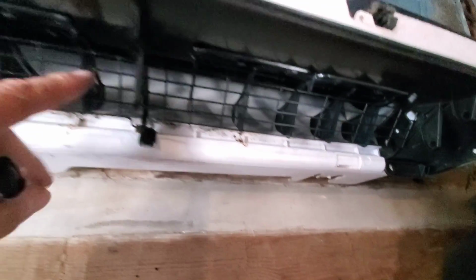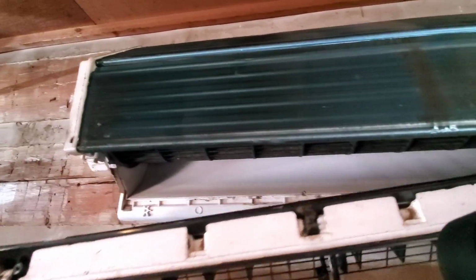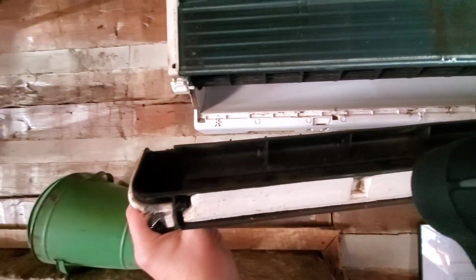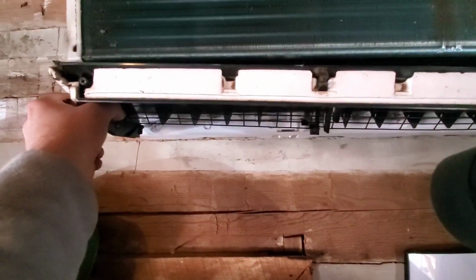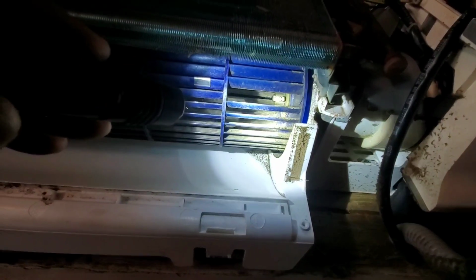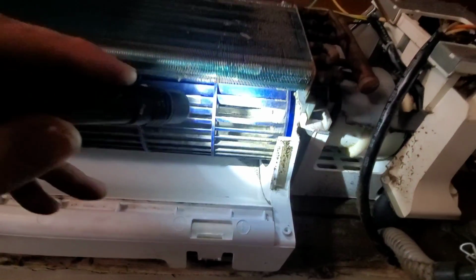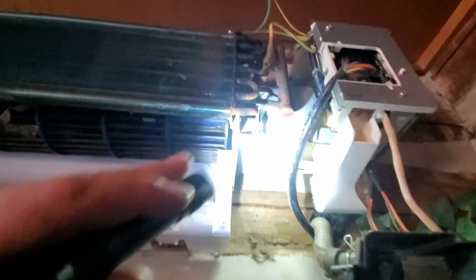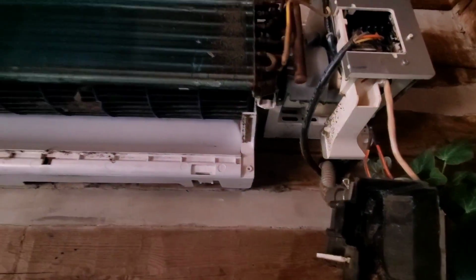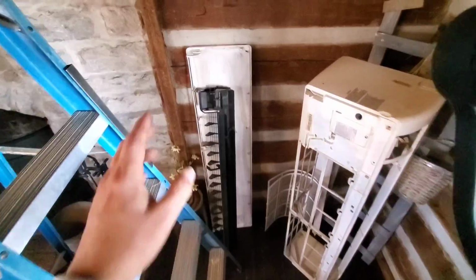All right, so now we got the drain pan, and we don't have to remove the wheel to clean it, but we're going to get it to where we can. So we just basically take our drain pan, not screwed on, so it's just pressed in here and it snaps in. And you can see it's pretty dirty too. So now we can look at our blower wheel. Nice, very nice. Phillips head screw. You can take that loose, and then you'll be able to slide the blower wheel off of the shaft of the motor. And to get the motor out, I've got some Phillips screws to take loose before I can get the motor out. Got the drain pan off.